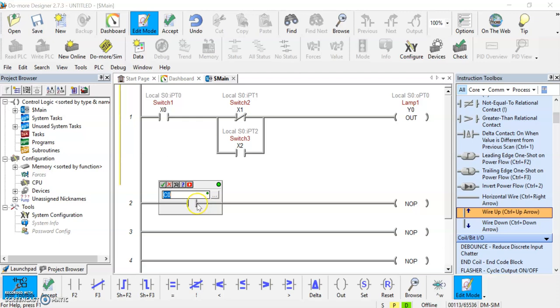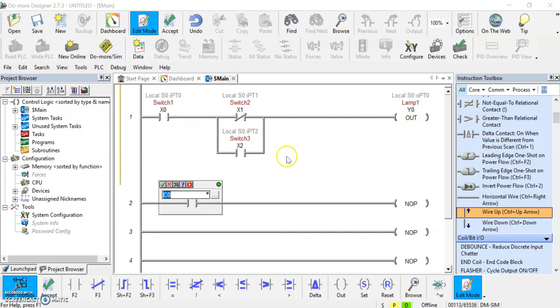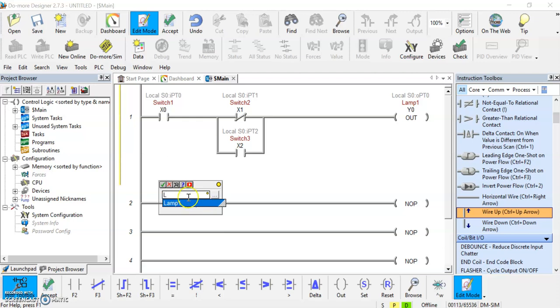If we follow the logic through and we get a switch closure here and a switch closure here, then this lamp should come on. Then if this reads a 1, it's going to say that this is going to write a 1 to this particular normally open contact here. So let's just call that lamp 1, and you'll see that in the program because I've already saved that, it's already in there. I'll just do that and it already populates it there.